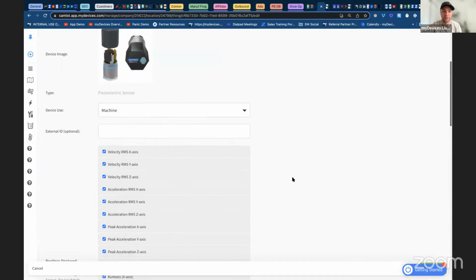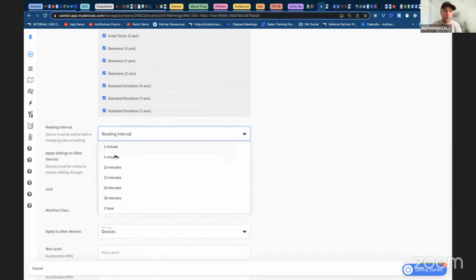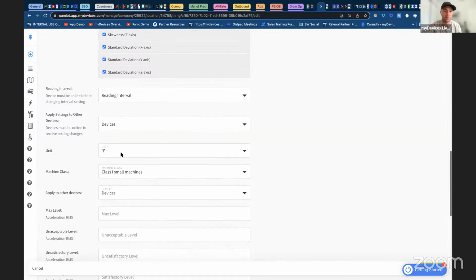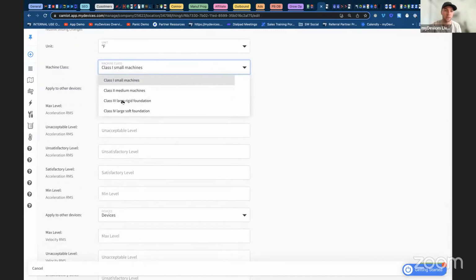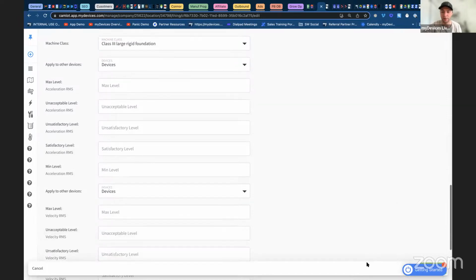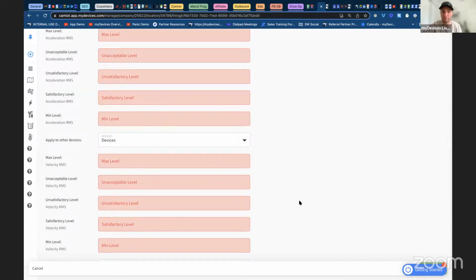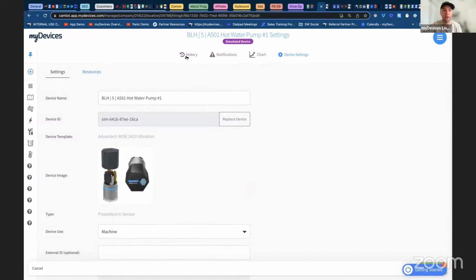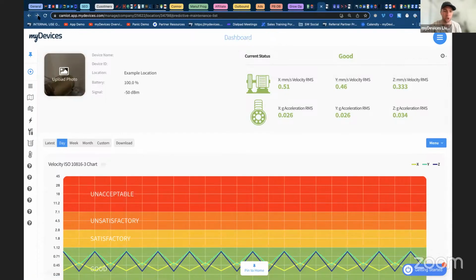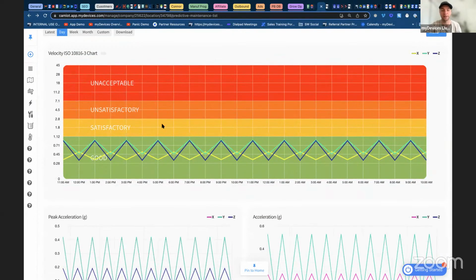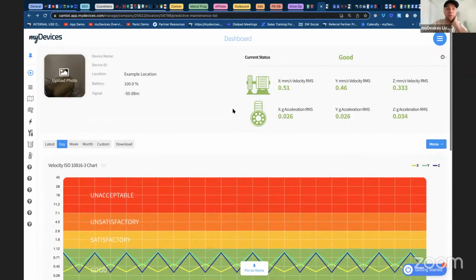There are also device settings, where you can configure reading intervals - every minute, 5, 10, 15, whatever - and what class machine it is. If I change this to class 3 as an example... I need to fill in the other info, but what that does is change this ISO chart based on the class of device you're putting the sensor on. Class 3 has a higher threshold for vibration, class 1 has a lower threshold, so these values will be a bit different.